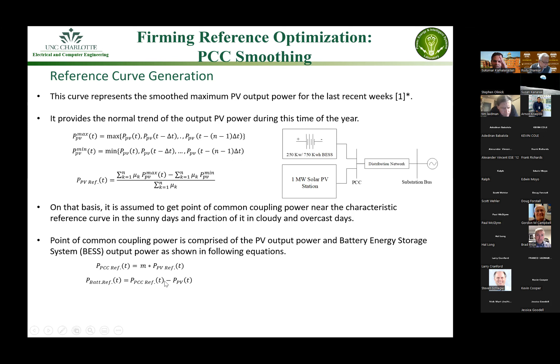That's the key aspect of this algorithm. Once we have the power coming from the point of common coupling, you can utilize that as a reference point for the battery by subtracting the PV measurement, which happens at the current time, not forecast.